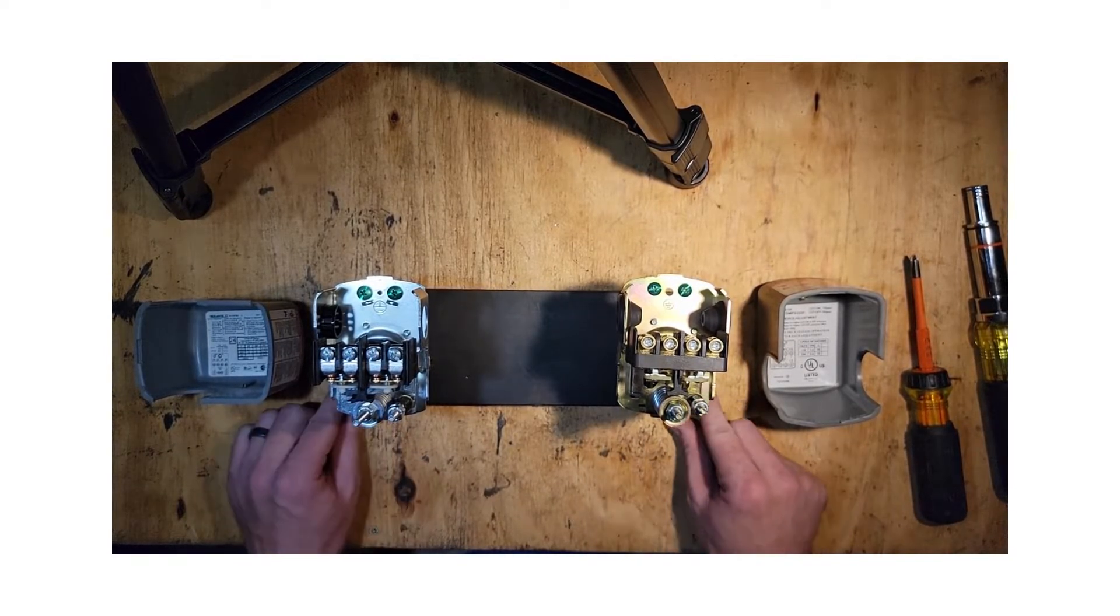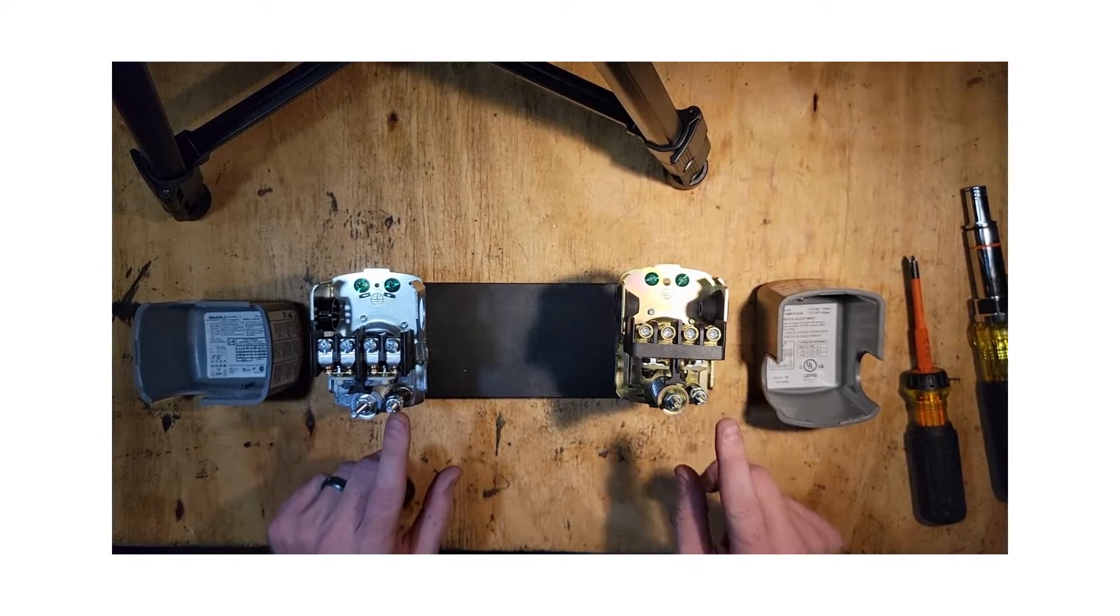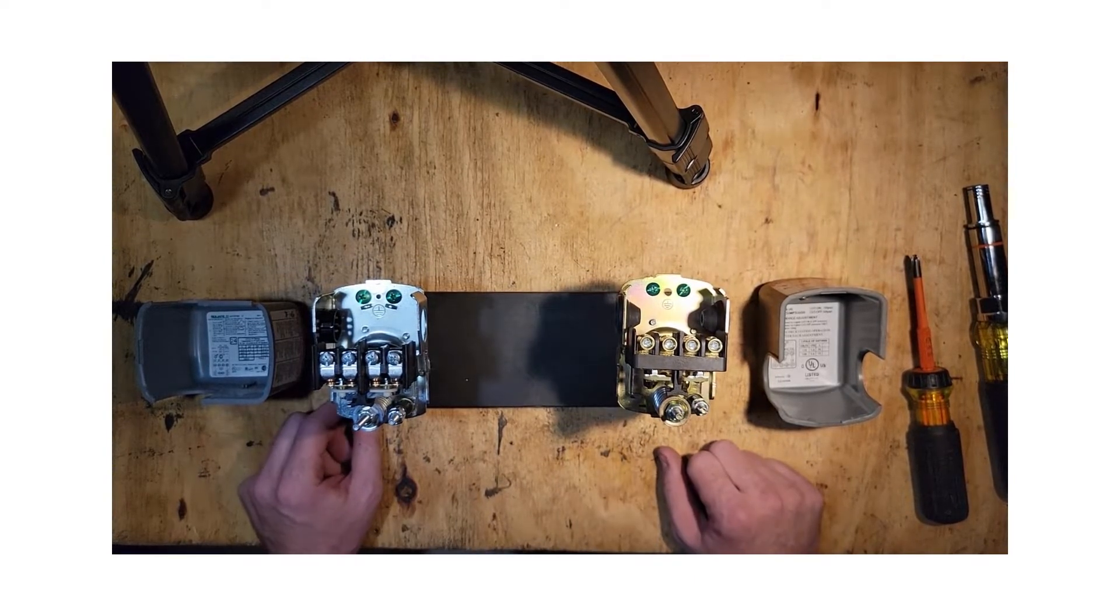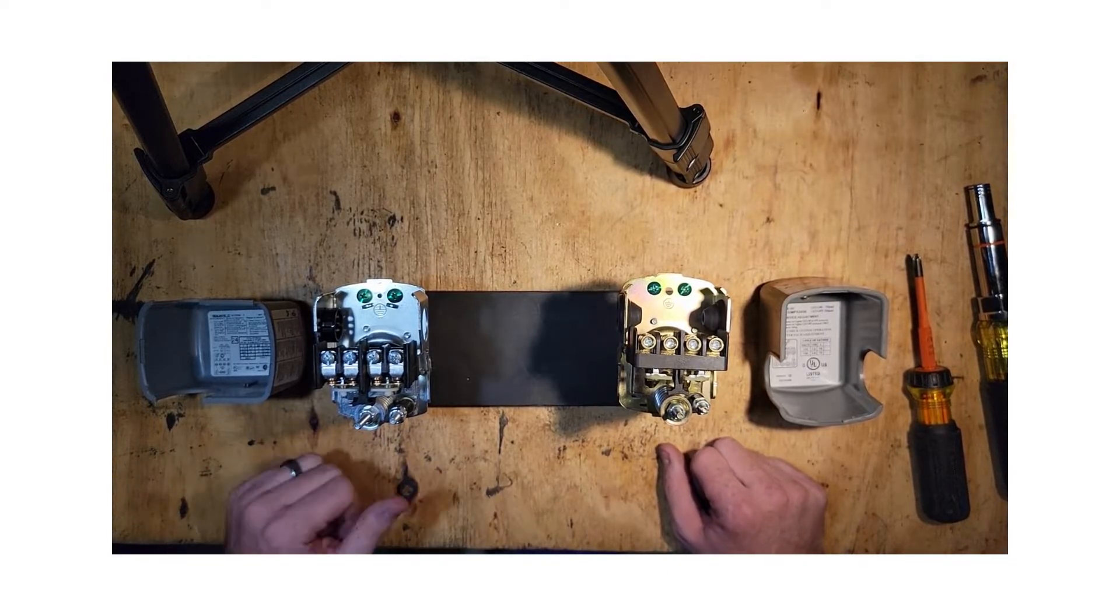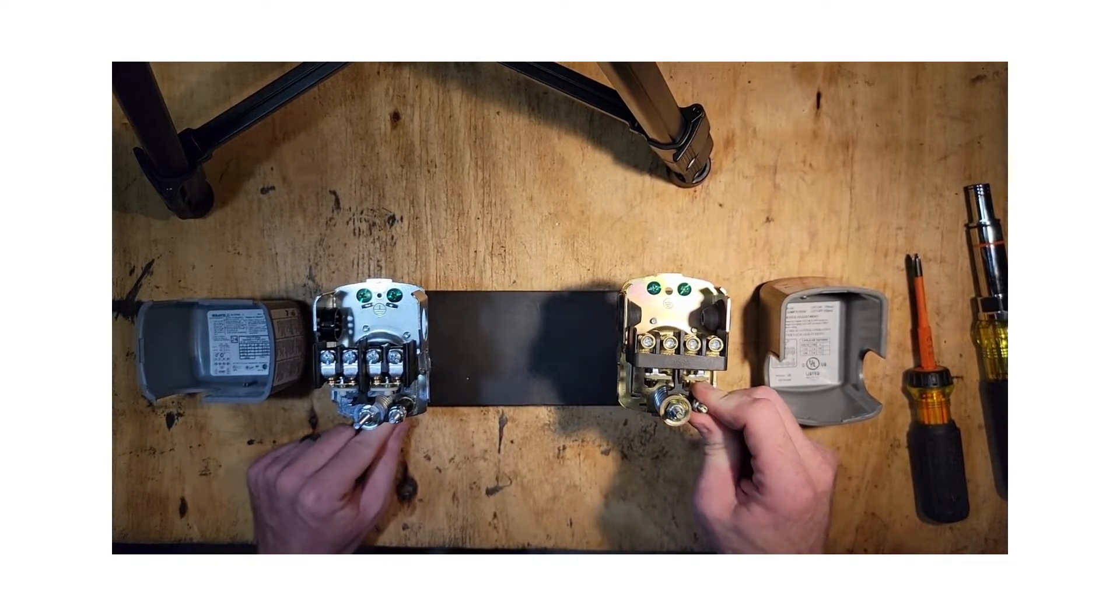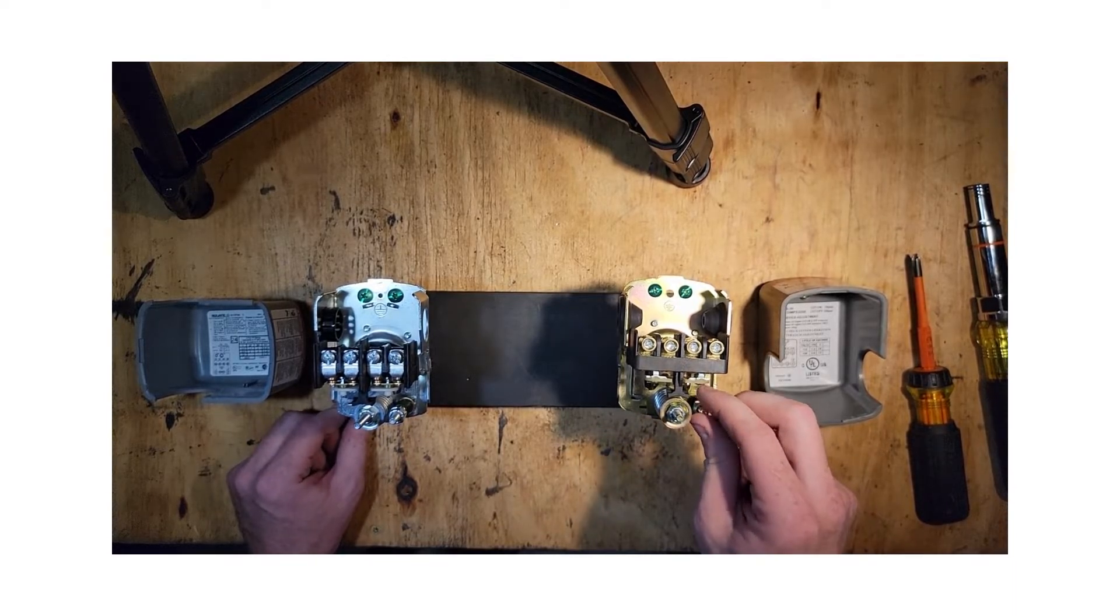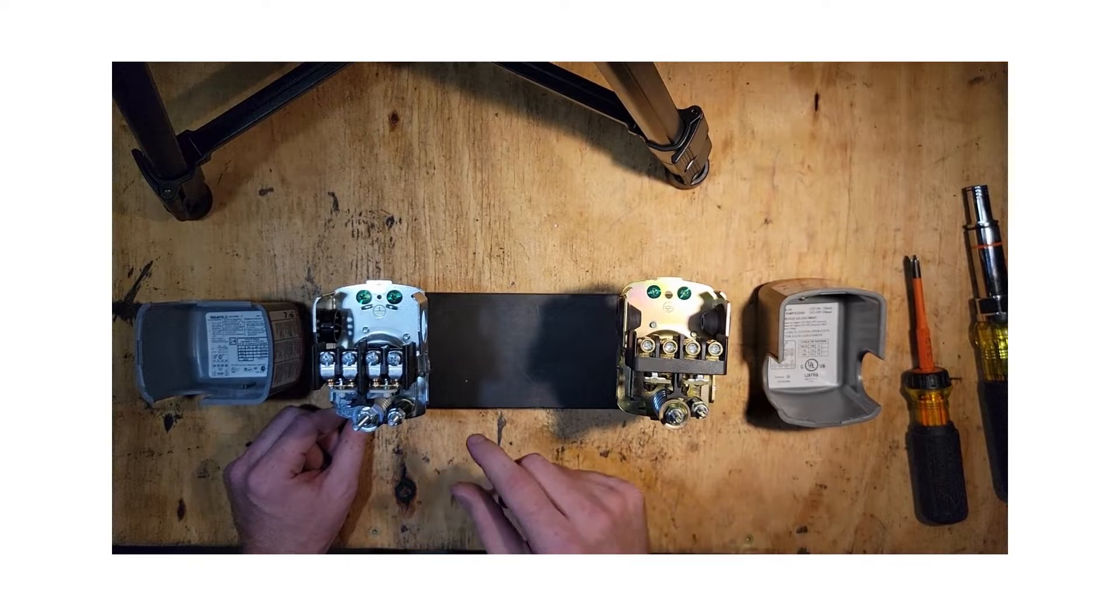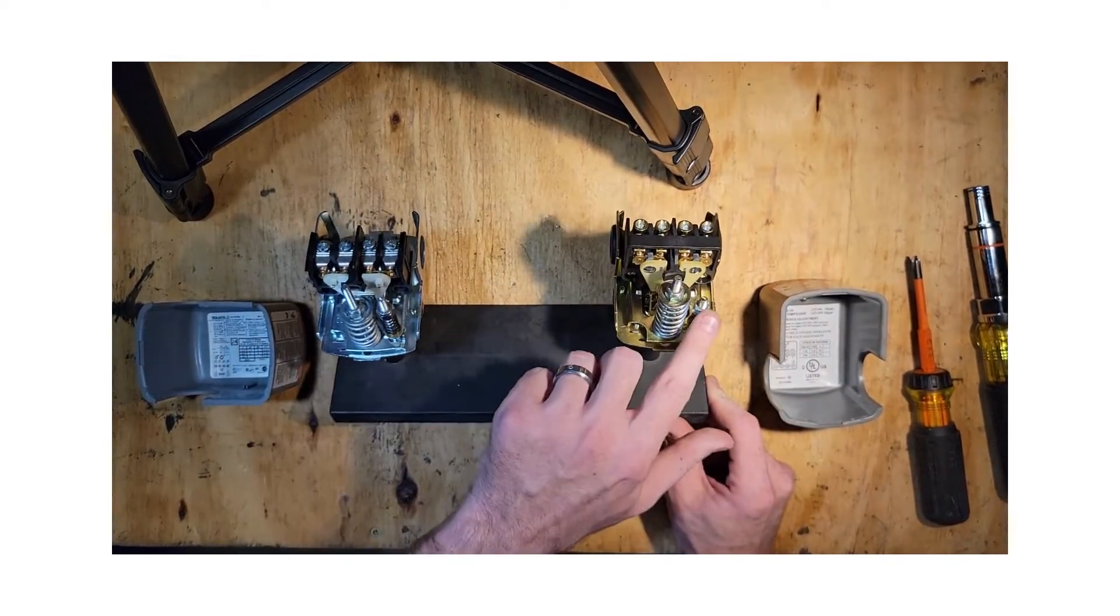Looking next at the smaller post, smaller nut here, that adjustment is just for the turn off or the cut off pressure only. So if I want to just change the pressure at which my pump turns off, I would only adjust the smaller spring loaded screw here.